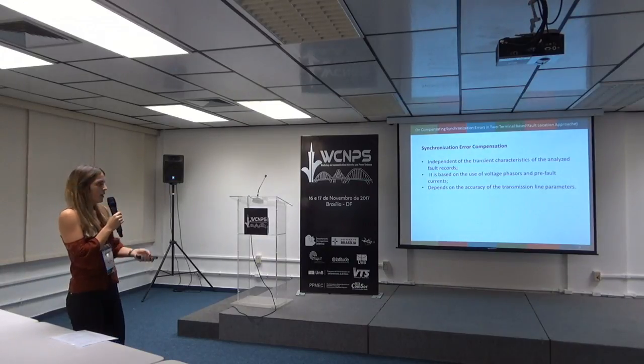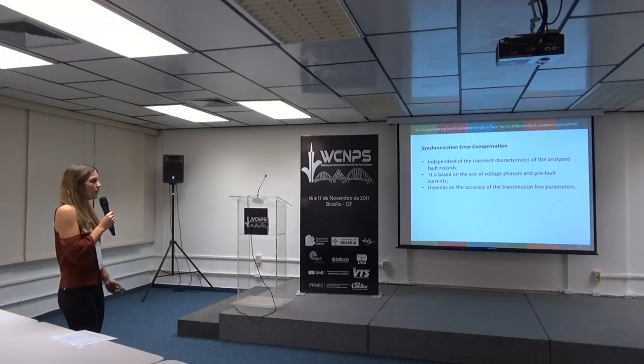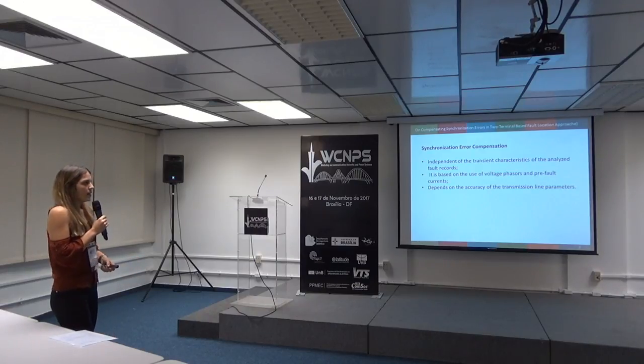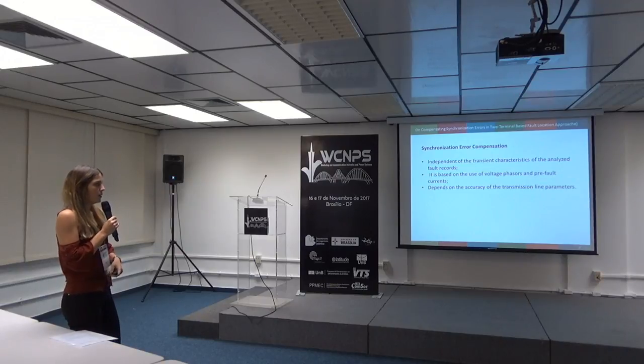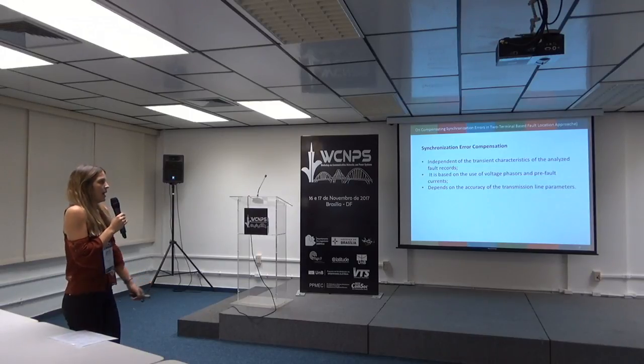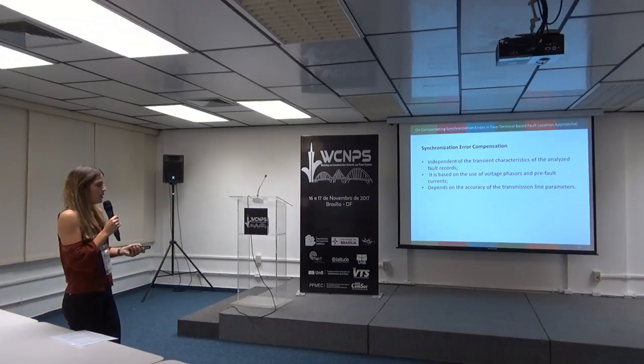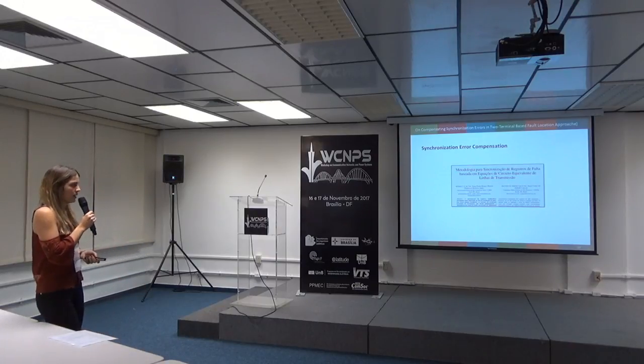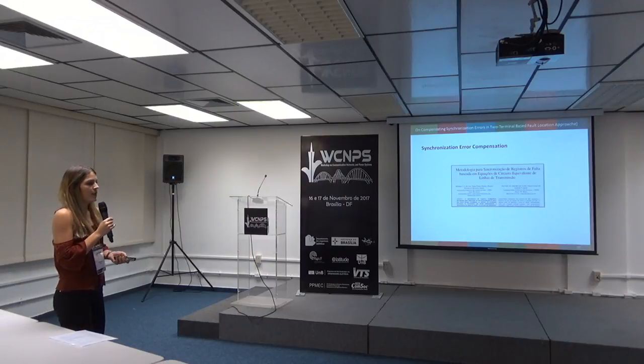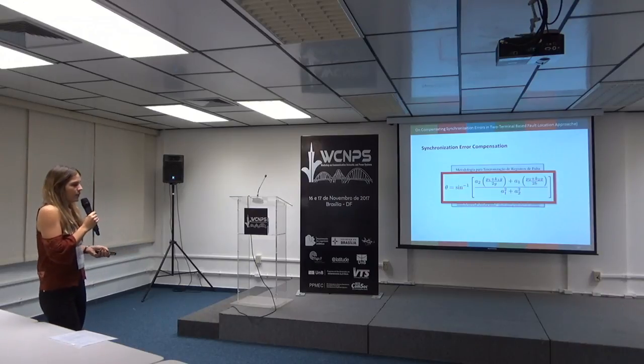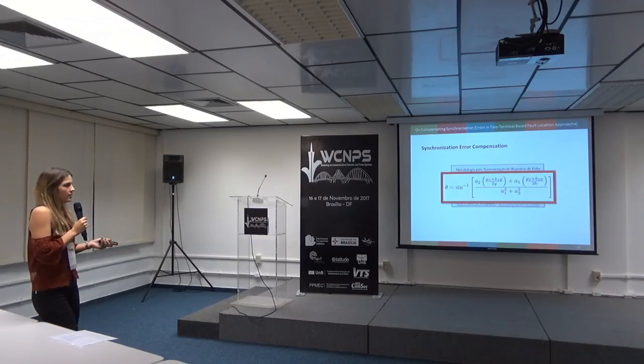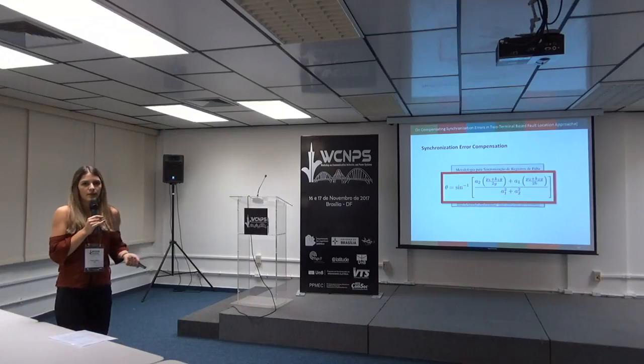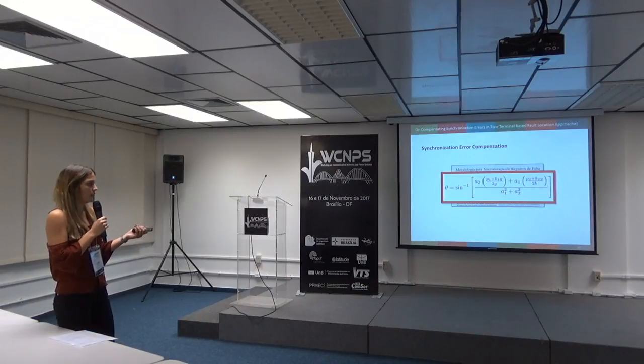The algorithm to determine the synchronization error is independent of the transient characteristics of the analyzed fault records. It's based on the fault voltage phasors and the pre-fault current, and depends on the accuracy of the line transmission parameters. This is the paper. And the synchronization angle is given by this equation. I will not present the maths, you can see it in the paper.